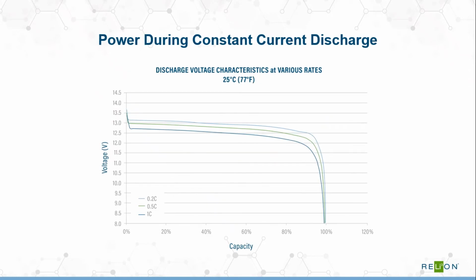Moving on, also power during constant current discharge. Lithium has little to no voltage sag. And looking back at that 50% rule with lead acid, the farther you discharge beyond 50%, the lower the voltage goes under load. So, most DC appliances like about 10.5 volts to function. So looking at this chart, we have our discharge voltage characteristics at various rates. And on our x-axis here, we have capacity, and our y-axis, we have voltage. And I want to put a line here right at the 90% part.